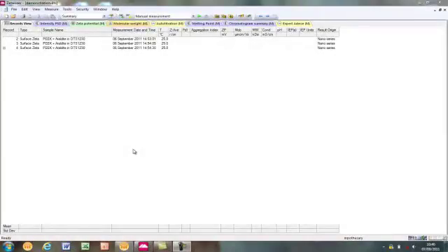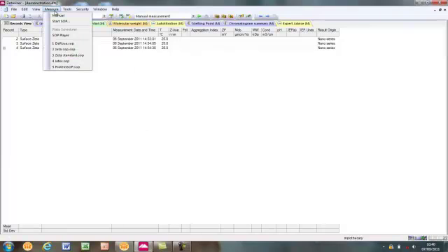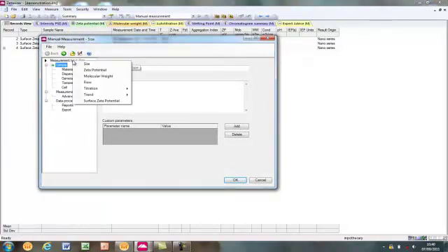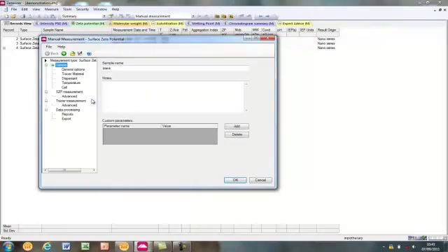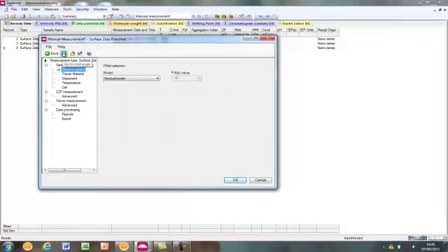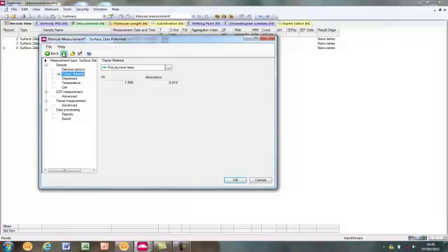The cell is now zeroed and the measurement can be performed. This is done by first preparing an SOP or setting up a manual measurement. Most of the settings will be familiar to those who have previously run particle zeta potential measurements. First, a surface zeta potential measurement must be selected under the measurement type option. The sample is then given a name. The general options allow an f(Ka) value for the Henry equation to be input. Next, the tracer particle sample type is selected. The type of medium can then be chosen.